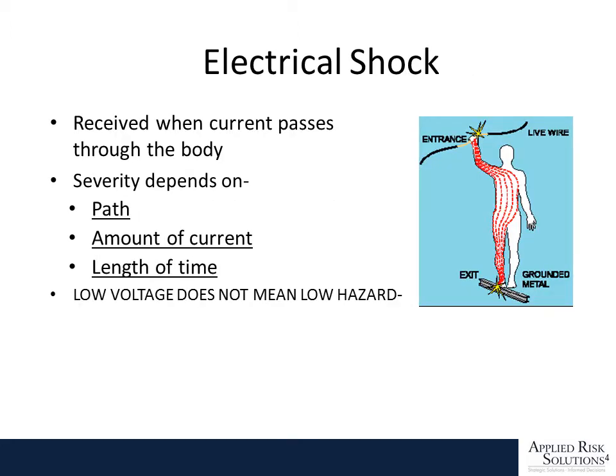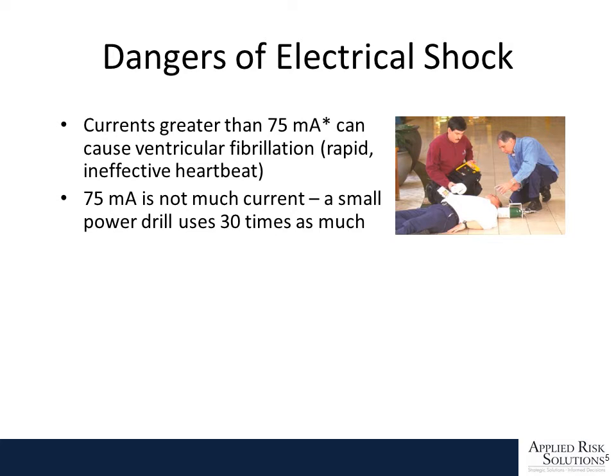Electrical shock. Electrical shock is received when current passes through the body. The severity depends on the path, the amount of current, and the length of time. And remember, low voltage does not mean low hazard. Currents greater than 75 milliamps can cause ventricular fibrillation. This is the rapid ineffective heartbeat. It's what happens when you have a heart attack. The heart doesn't fully constrict and beat. It just kind of flutters. 75 milliamps, not much current. A small power drill uses about 30 times this much.